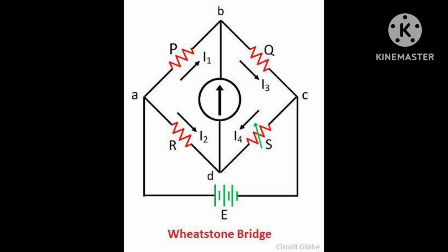Now I will tell you how to determine R. Here R and kappa are both known: R you will come to know by the Wheatstone bridge, and kappa from the standard chart. Then you will easily find the L upon A value, which is the cell constant. Once you know the cell constant, that's enough, its value is fixed.